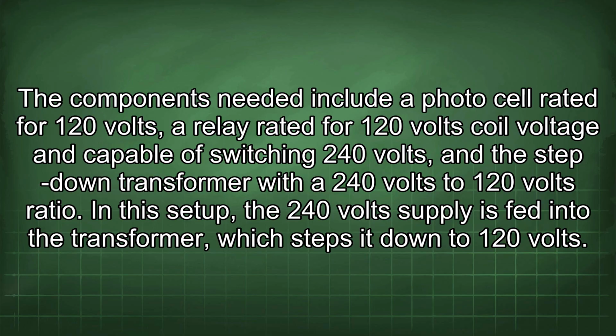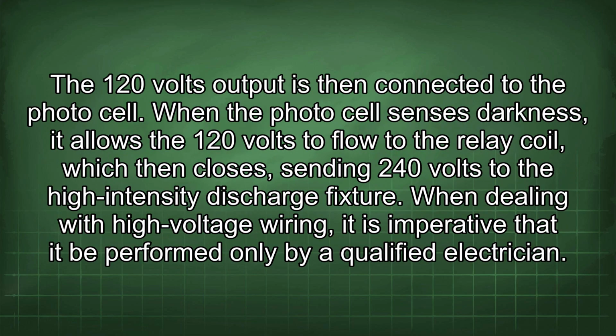The components needed include a photocell rated for 120 volts, a relay rated for 120 volts coil voltage and capable of switching 240 volts, and the step-down transformer with a 240 volts to 120 volts ratio. In this setup, the 240 volts supply is fed into the transformer, which steps it down to 120 volts. The 120 volts output is then connected to the photocell. When the photocell senses darkness, it allows the 120 volts to flow to the relay coil, which then closes, sending 240 volts to the high-intensity discharge fixture.